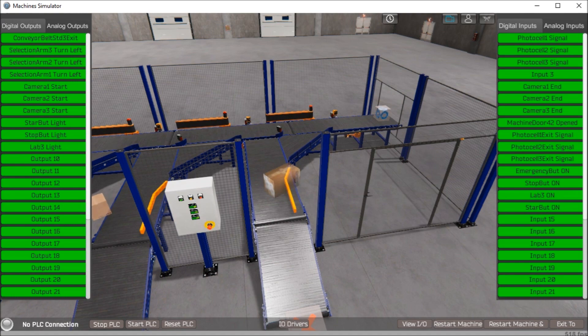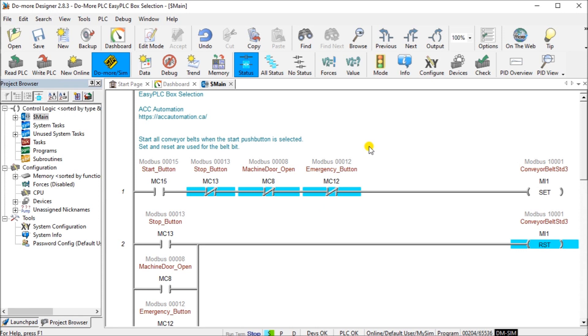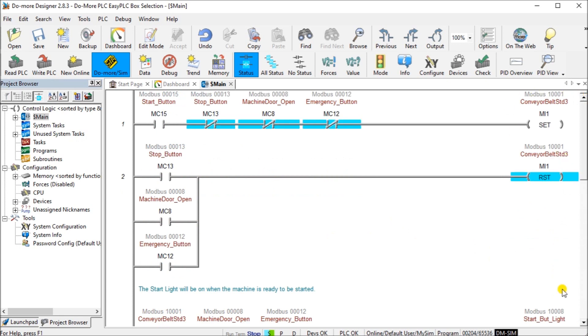The next step is step four: development of the PLC program. If we call up our Do More Designer, we have all of our inputs and outputs mapped to our Modbus locations. The first thing we'll look at is starting our conveyor belt, which is our first output. We need the start signal, and we must not have the stop, machine door open, or emergency stop — then we will start that conveyor belt using a set instruction. We reset it when we have a stop button, machine door open, or emergency stop.